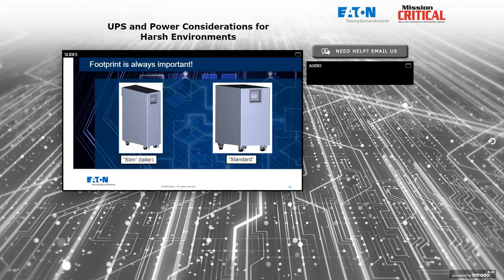Okay, moving on here. Just like in any application that we've seen in the critical power market, footprint is more important than we expect. So taller, slimmer systems are usually more desirable, but you have to keep in mind in some of these environments, the ceiling is going to be lower. The vibration, and particularly in marine environments, is not going to allow a tall, slim UPS unless it is bracketed at the top, as well as vibration isolators on the floor. But in general, if you have a choice for a smaller footprint, the client is going to be more likely to use that because footprint is king.